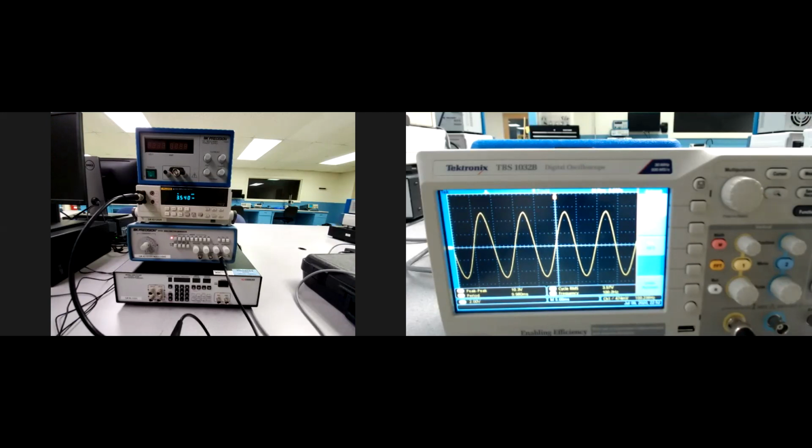It's around 2 megahertz, spoiler alert, but we are not focusing on calculating that. The oscilloscope is our reference. What we need to find out is the multimeter's cutoff frequency.